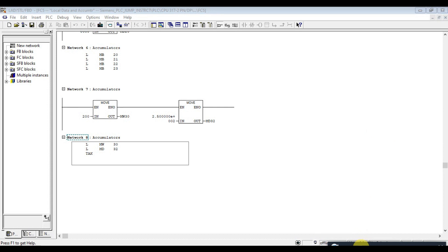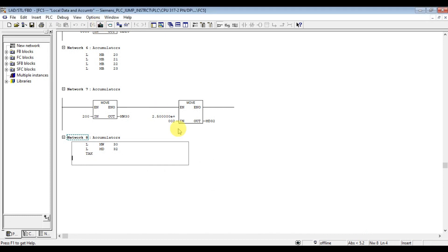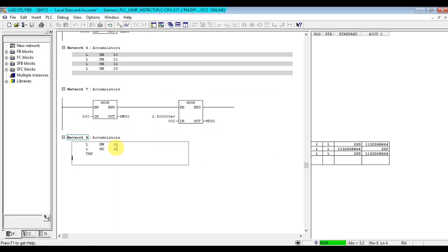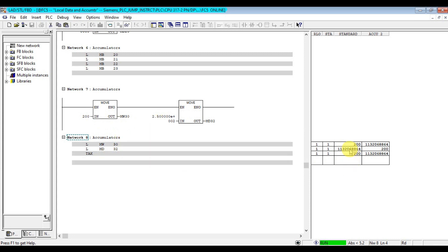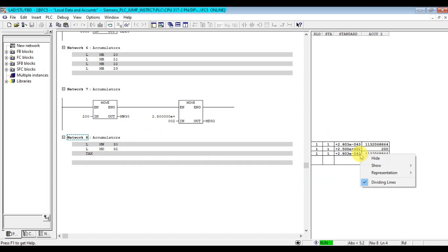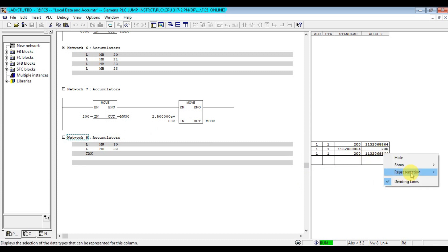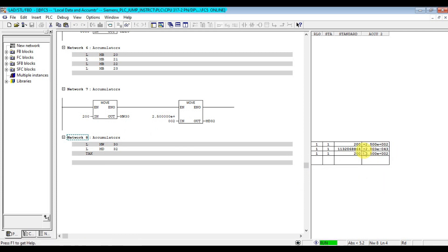I have added the TAK toggle instruction here. It will interchange the two accumulators: Accumulator 1 will be shifted to Accumulator 2 and the value stored in Accumulator 2 will be shifted to Accumulator 1. After download: 200 is loaded on Accumulator 1 and 250 is loaded on Accumulator 2. When we execute toggle, 200 moves to Accumulator 2 and 250 moves to Accumulator 1. They interchange the values.